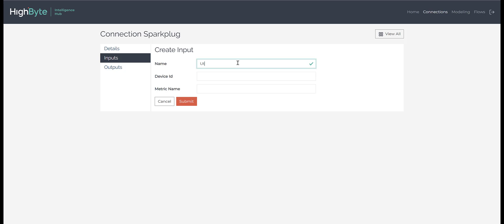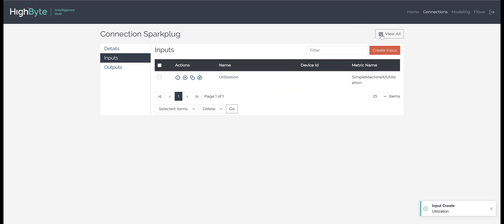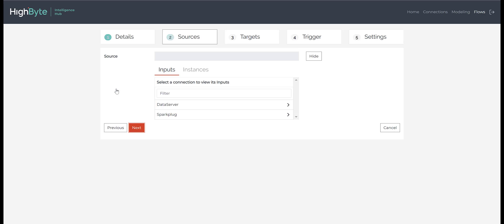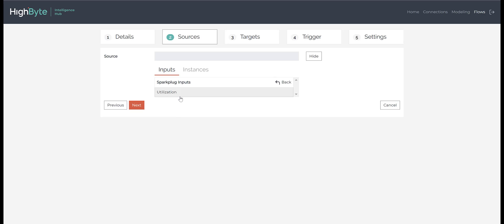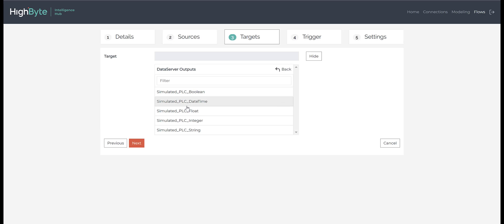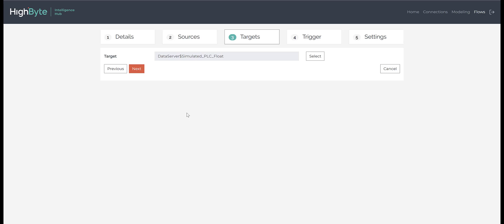We will give the input a unique name. Since this metric is associated with the EON, we do not need to assign a device ID. However, we must supply a metric name. This is simply the path to the input as we saw in the Ignition Sparkplug namespace. All that's left to do is to wire up a flow and send the data to OPC. Here we will select the Sparkplug input as the source and map it to an OPC output as the target, and then connect the flow.